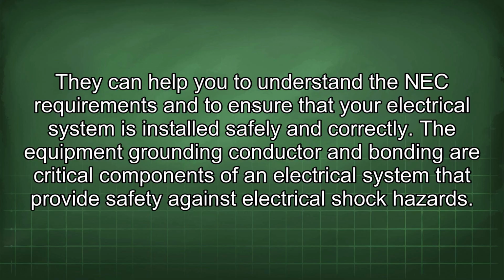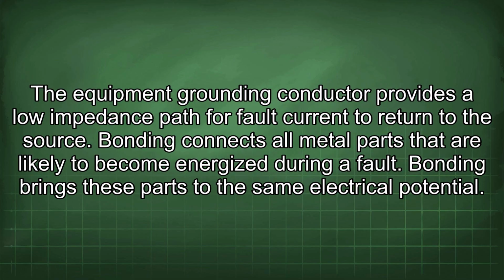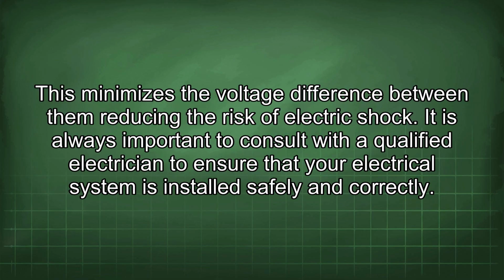The equipment grounding conductor and bonding are critical components of an electrical system that provide safety against electrical shock hazards. The equipment grounding conductor provides a low impedance path for fault current to return to the source. Bonding connects all metal parts that are likely to become energized during a fault. Bonding brings these parts to the same electrical potential. This minimizes the voltage difference between them, reducing the risk of electric shock. It is always important to consult with a qualified electrician to ensure that your electrical system is installed safely and correctly.